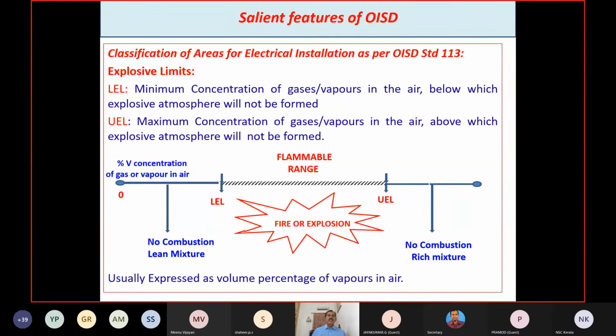Here is the maximum concentration of gases and vapors in the air, above which the explosive atmosphere will not be formed, and it will not get ignited even if you introduce any source of ignition. That is UEL. Here the concentration of gases and vapors will be more, and the oxygen is not sufficient to have the right proportions. So that is called a rich mixture. Both the lean mixture and the rich mixture do not support any combustion.